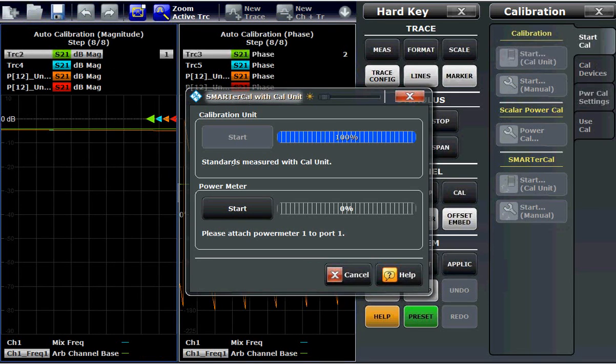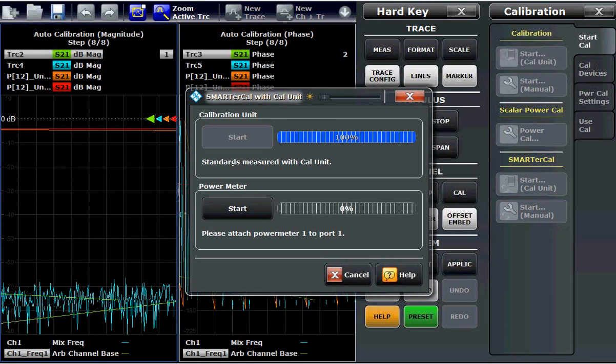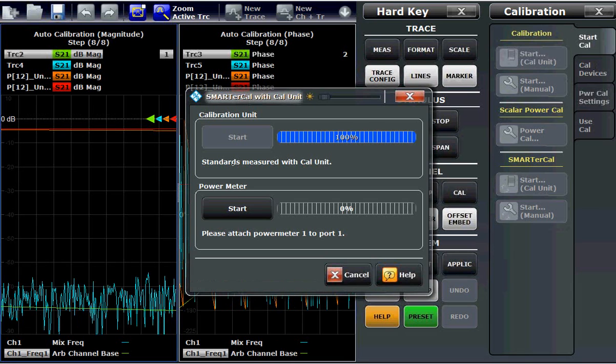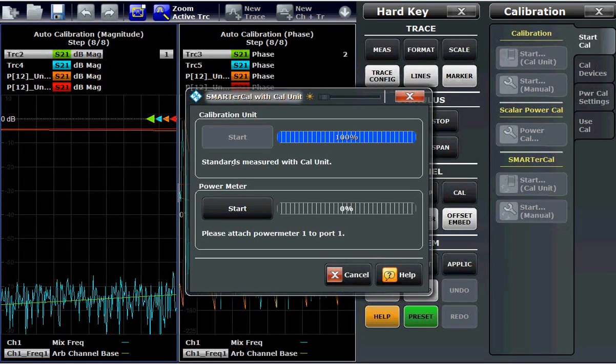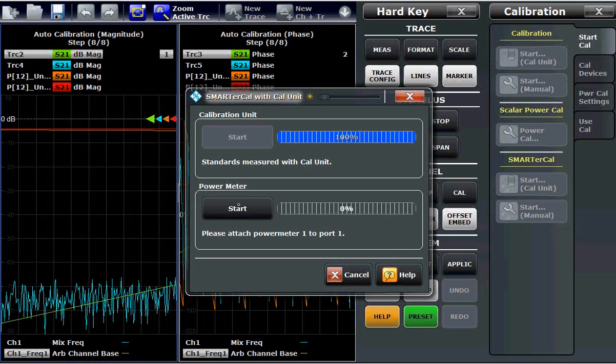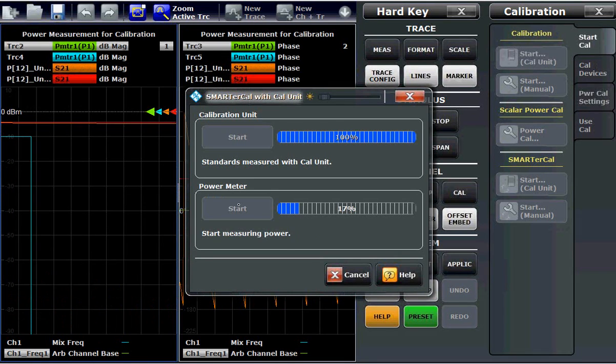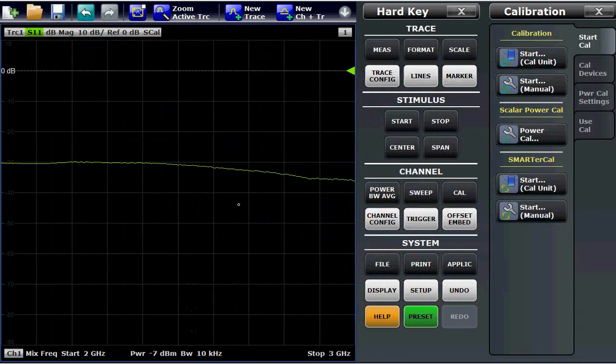After finishing the system error correction calibration, we have to do the power calibration, and therefore we have to connect port number 1 to the power meter and press the Start button. So right now the Smarter Cal has been done successfully. That can be shown here by the letter S in front of the Cal sign.